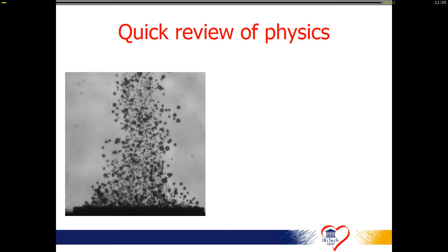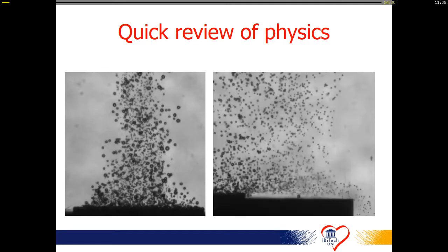And one of the main points is the fact that when a fluid is not moving, every GME, gaseous GME, will actually go up. And that's very simple, so when we have very low flows, it's very easy to remove them. But the moment we actually start to move this fluid, and in this case, this would be at the right, so the fluid is moving in this way, you can see immediately the smallest bubbles are actually dragged inside the fluid. And this is a basic concept. We should never forget that if we want to remove them, velocity will be an issue.